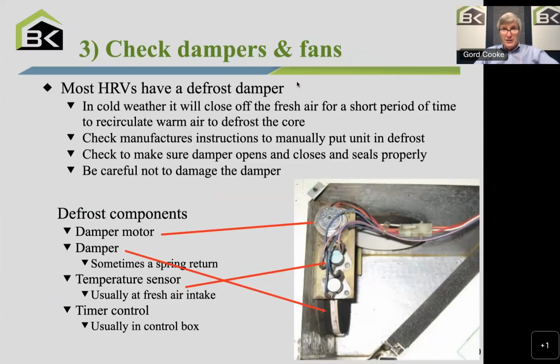And what a defrost does, this little damper mechanism, is it temporarily closes off the outside air and recirculates warm air through the fresh air side of the core. So it defrosts the core from the fresh air side. This is very common. 90% of HRVs sold, maybe 85, have this kind of damper defrost. It's not in defrost all the time. It's typically in defrost for 5 to 10 minutes out of each hour.